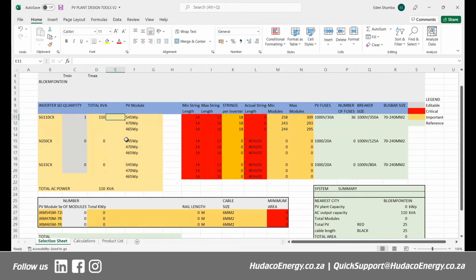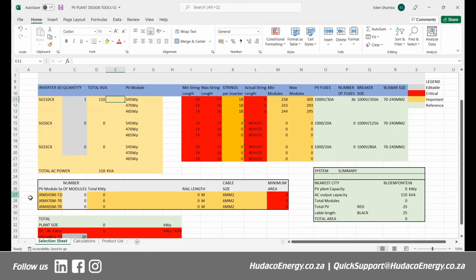Then, if you go down here, let's say I've chosen to use 470 watt peak panels instead of 545s, so I know my choice should be in the range of 243 to 293 panels. Let's say I choose the middle ground, round about 265 panels. Immediately it shows me that this amounts to 124.55 kilowatts peak, which is the total size of my plant.